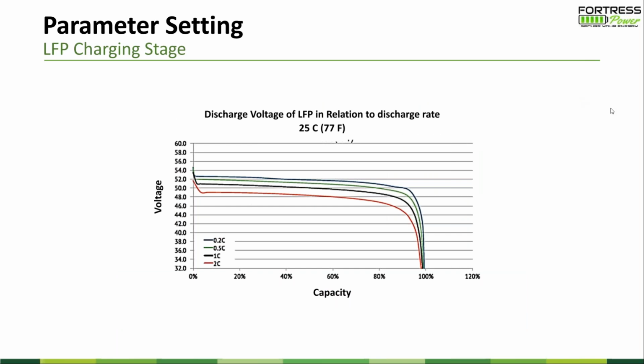On the charge and discharge curve, as mentioned, compared to lead acid, the voltage drop over the whole process is very minimal. We look at a 5-volt drop from full charge to 80% depth of discharge. The customer always asks, can we tweak up the discharge voltage and the charge voltage a little bit so that we can squeeze a little more energy out of the battery? Don't do it. The last 0.5 volt of discharge doesn't give you much, and the last 0.2 volt of the charge curve doesn't give you much energy. You try to keep your system healthy, just stay with the parameters we recommend. It's fully tested, and we verified it in multiple situations. It's no problem. If anything goes outside of it, it might get a little bit tricky when you do the system. Let's go to the next slide.